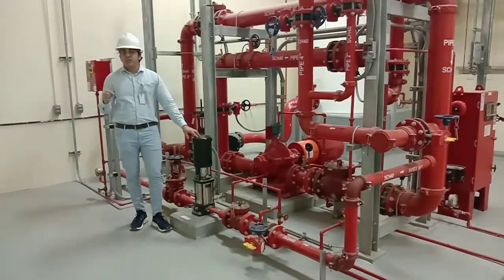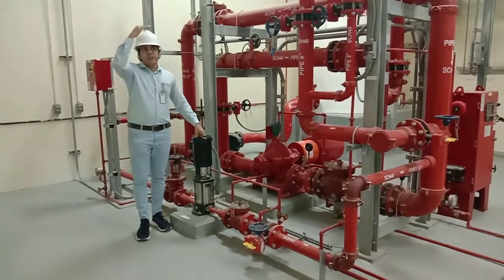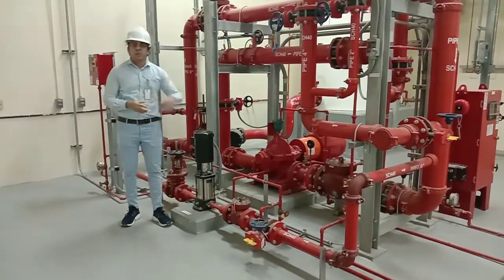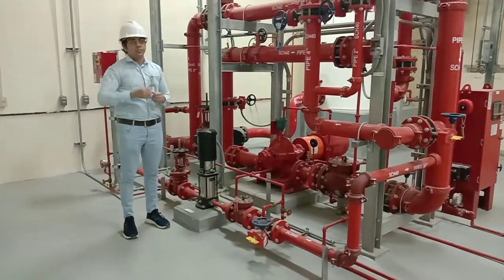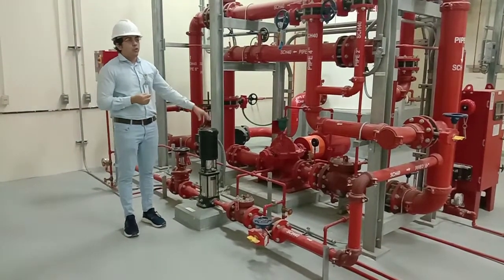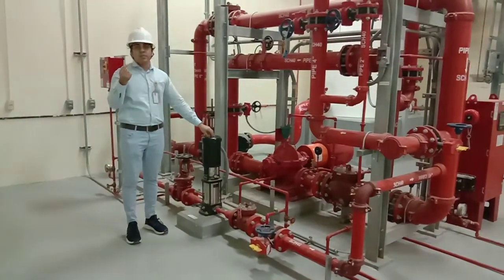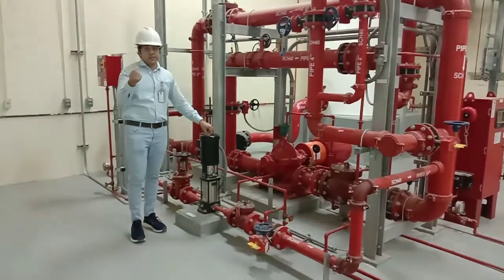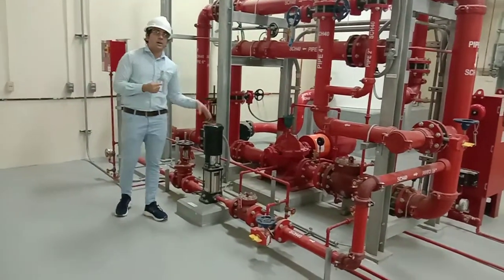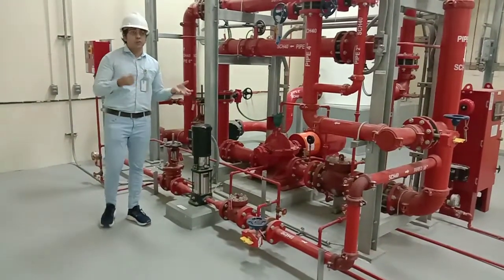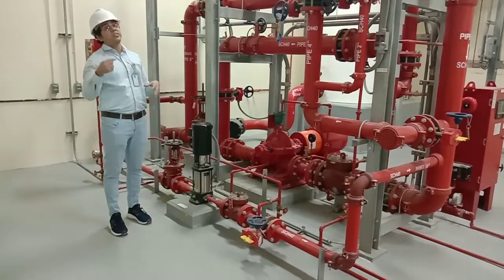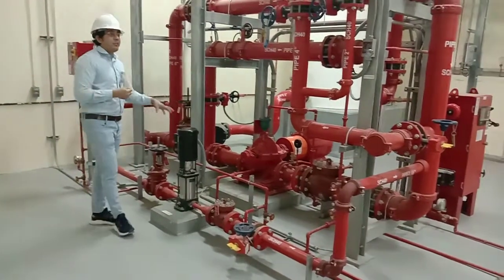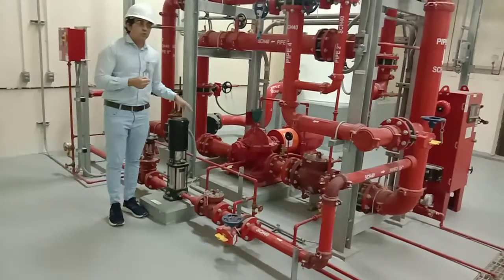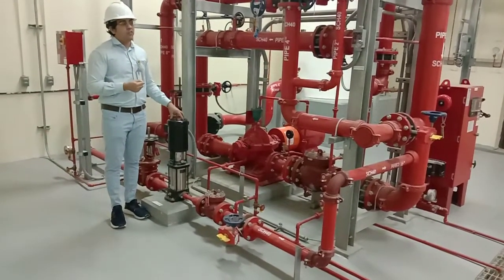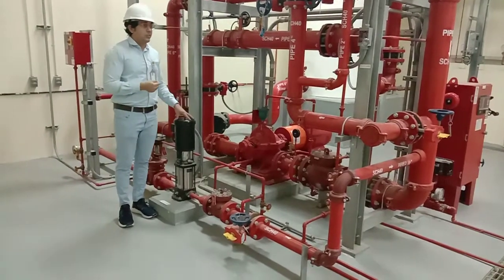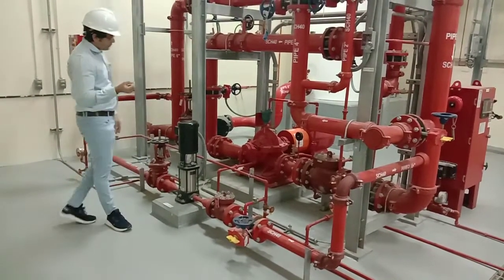The 1% is only for the underground fire water network. Coming to the above ground network, suppose your fire protection system is going to protect a sprinkler system, right? In that case, the flow of the jockey pump should be at least equal to the flow of the minimum K factor sprinkler. We have a sprinkler with a K factor of, let's say, 5.6 as per NFPA 13 and a minimum pressure of 7 psi. That sprinkler will give us 15 GPM of flow. So we need a jockey pump of 15 GPM in our case for the above ground or sprinkler system.